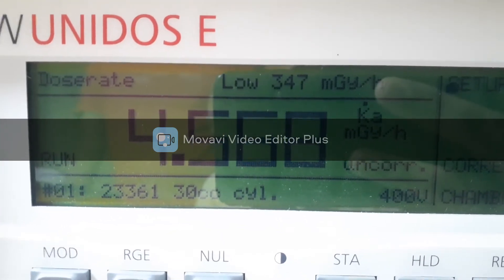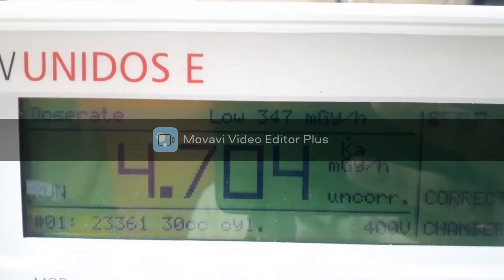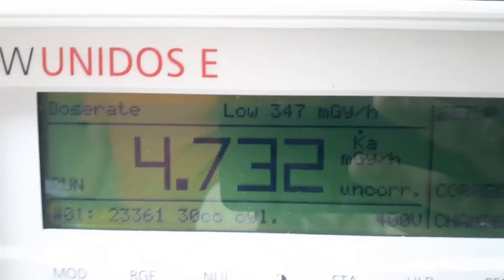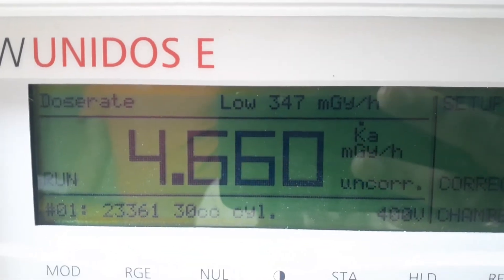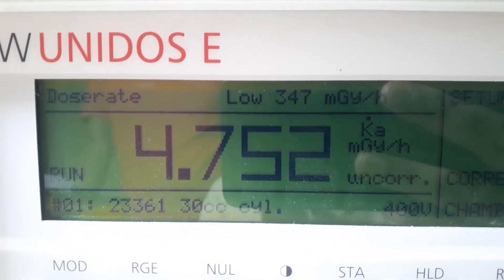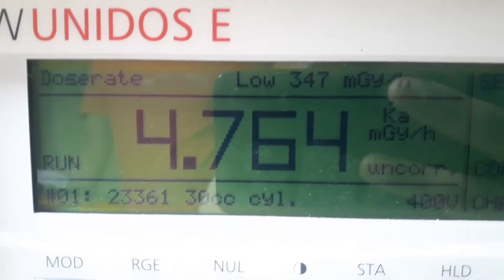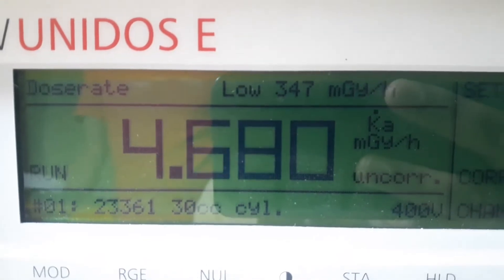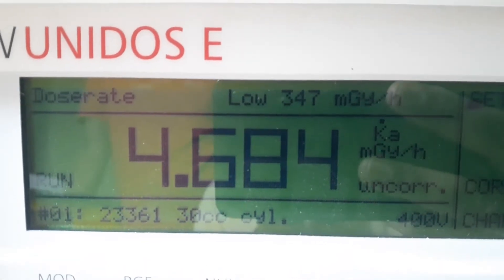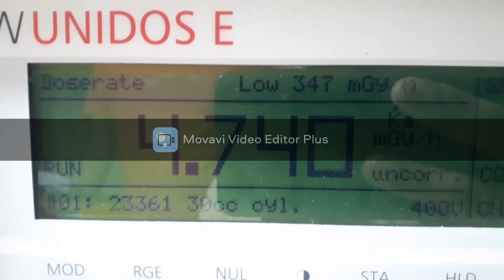This is the leakage radiation when the window is closed, at 1 meter distance. The maximum reading is 4.8 milligray per hour — I can confirm 4.8.